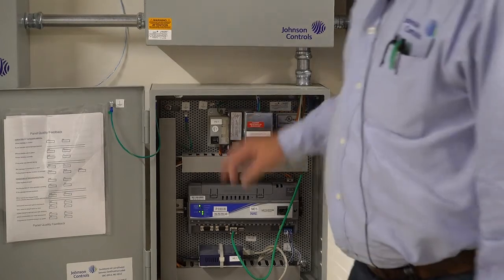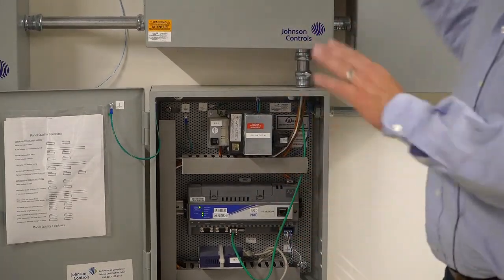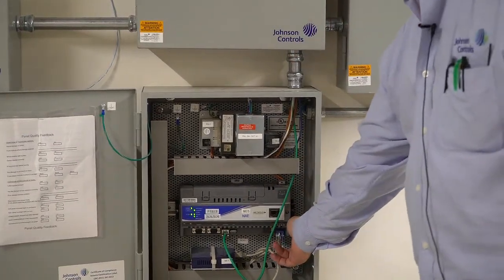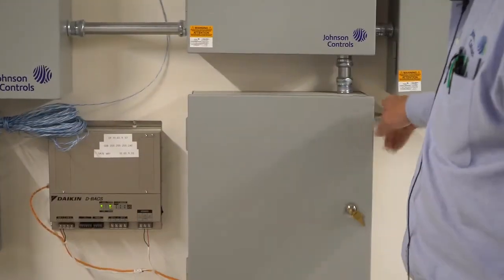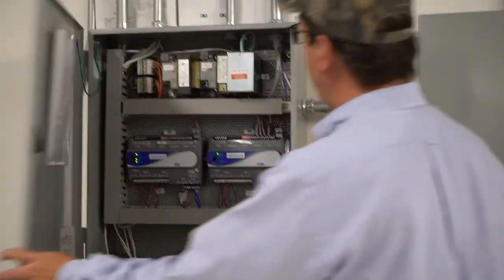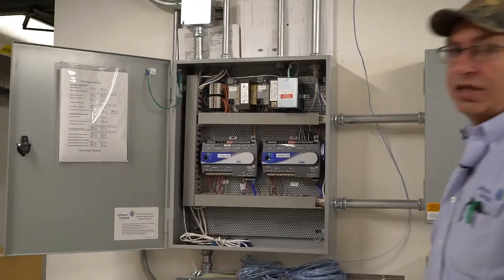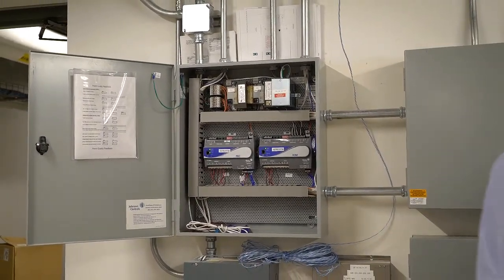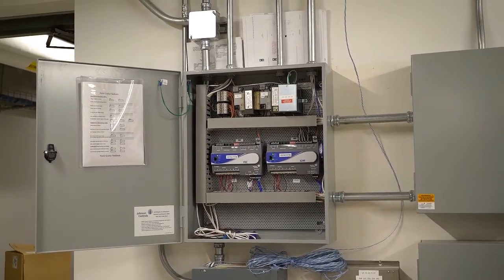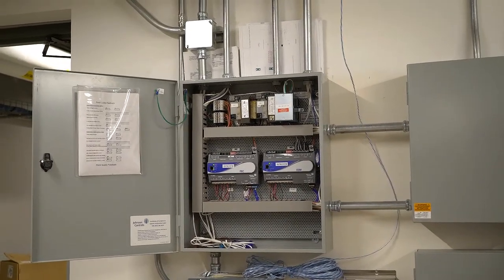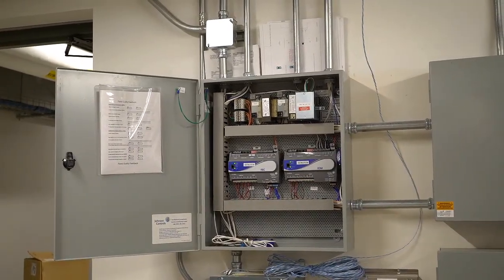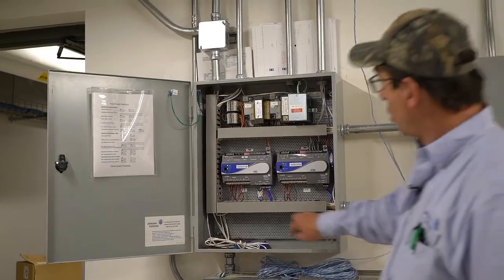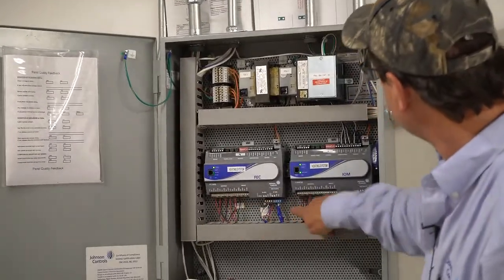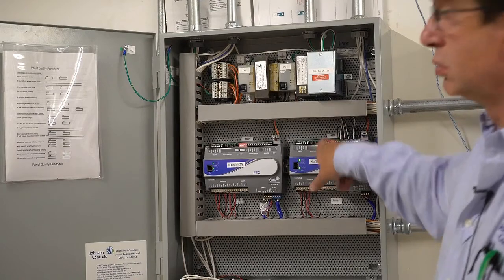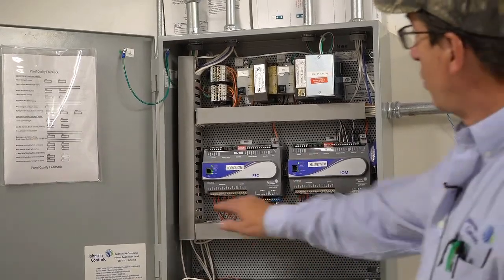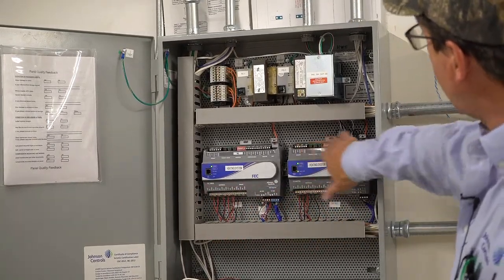Okay, so that's the main brains. Everything else that we're going to show you comes in and connects to these FC trunks. So we're going to start over here. This is the heating system panel. This will take care of the hydronic hot water pumps, the VFDs, the heat exchanger valves, all of the sensors. And all of those points are wired in down here and up here. The bottom are inputs, the tops are outputs.